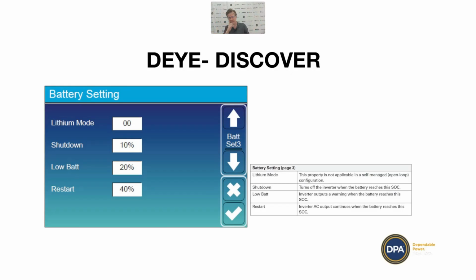So don't set your shutdown to 2% or something like that. 10% as a minimum, but I would probably have it more like 15. And then the low bat is just the alarm when it's going to start complaining about it. And then restart, we've got 40% here. Maybe you'd even have it higher because once it's switched off, the inconvenience has already happened. So you may as well let it all come up and be nice and healthy before anything else happens.